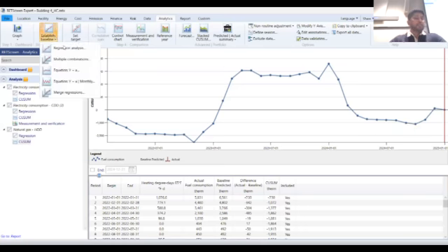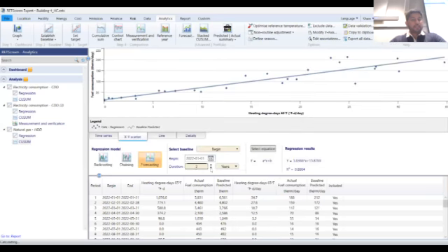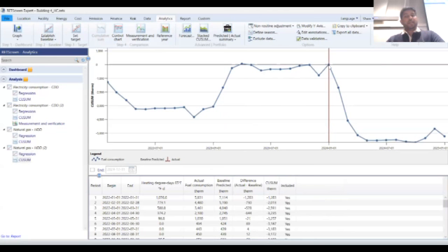Again, what I need to do is create a regression analysis. Now I know my baseline. I run the analysis again, but instead of 3 years, I change my baseline to 24 months, which is the whole of 2022 and whole of 2023, because my savings will start from 2024 onwards. My values changed. I do cumulative sum, and again, you see how it drops immediately after 2023.